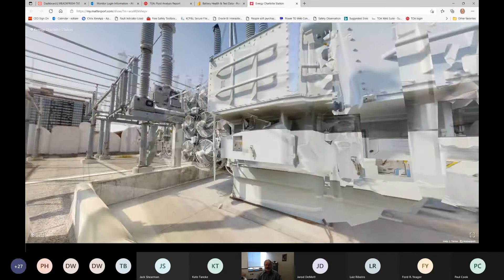Behind here is a desiccant breather - let's see what the color of the desiccant is. When the fans come on in the summertime, we get a temperature alarm, so let's see if all the fans are running. We simply pull up that image and take a quick peek to see what it is. If the fan's not running, machine learning should tell us, hey, the fans came on and these 3 should be running and these 3 should not be running, and there's a discrepancy in the data.